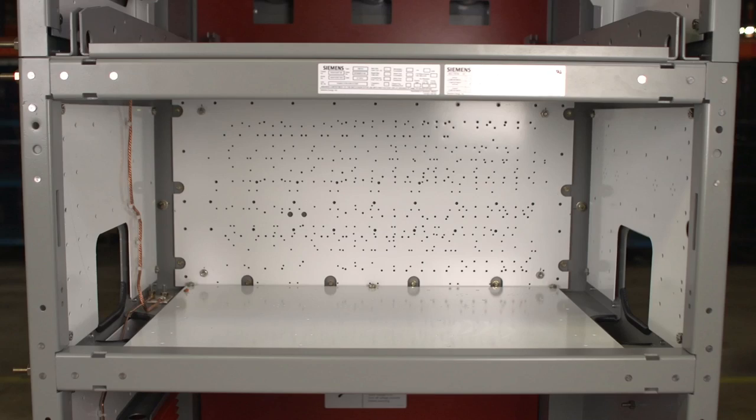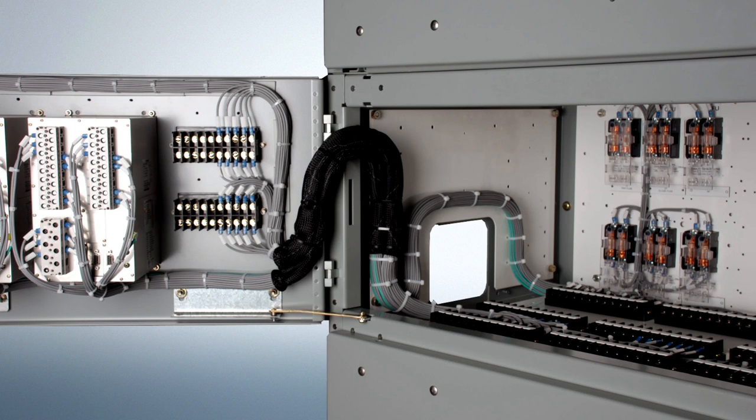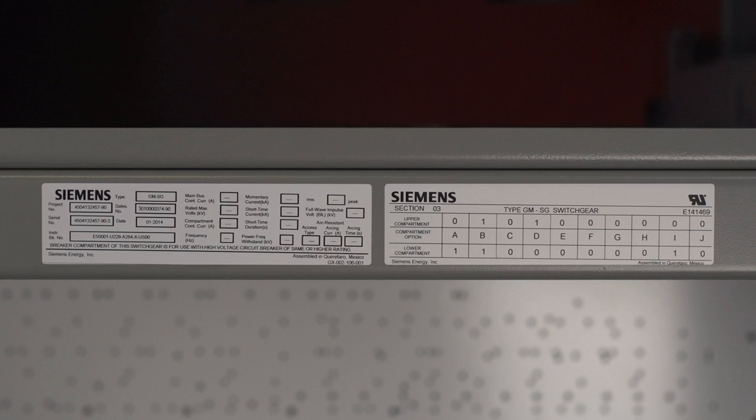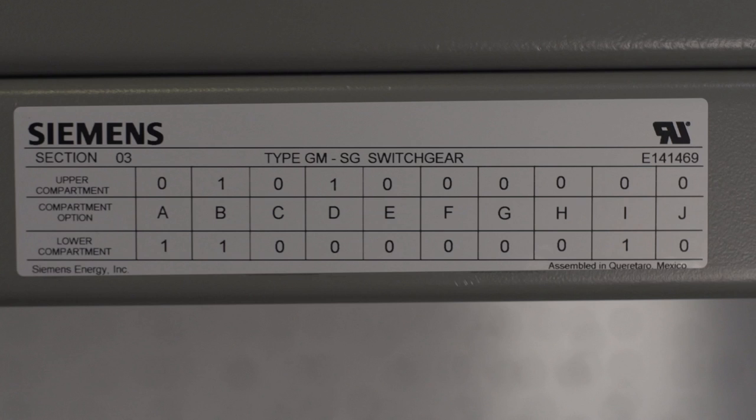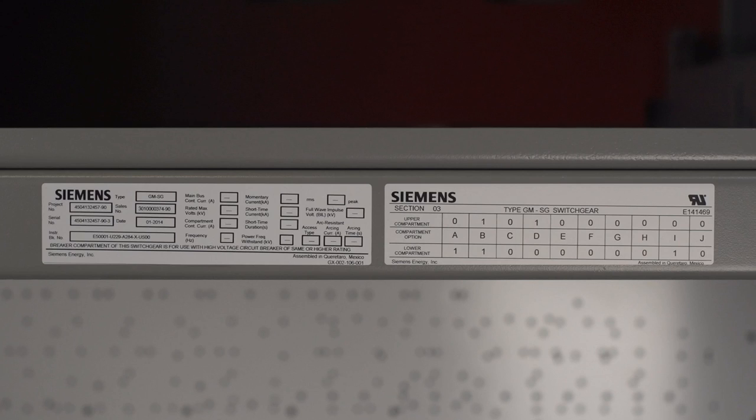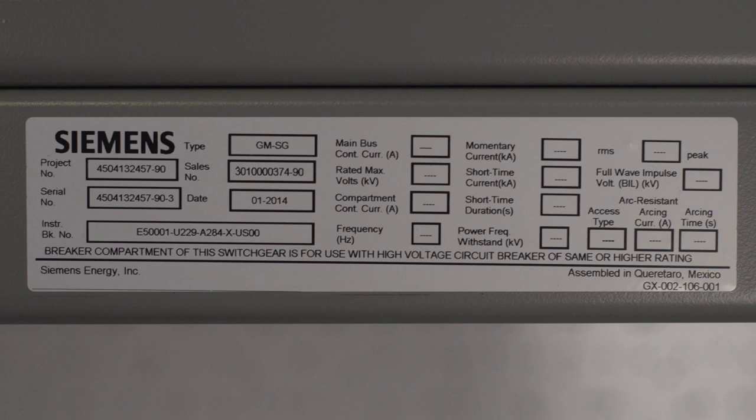Siemens GMSG switchgear also features a low voltage auxiliary compartment. The auxiliary compartment has removable white interior mounting plates. The white finish makes it easy for installation and service personnel to locate wires. Fuse blocks, terminal blocks, interposing relays, auxiliary relays and other devices can be mounted to these panels. You'll notice there are two labels on this compartment. The rating label describes the type and configuration of the compartment and the ratings of that particular GMSG skeleton section. The second label is the UL component recognition label. It details what section of the equipment was manufactured in the Siemens factory so the rest of the equipment from our OEM partner can be certified.